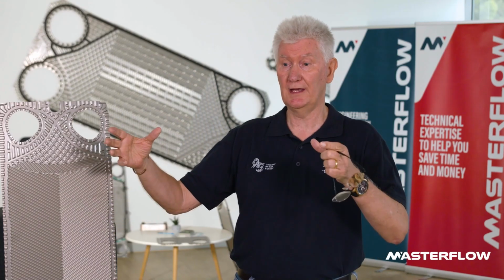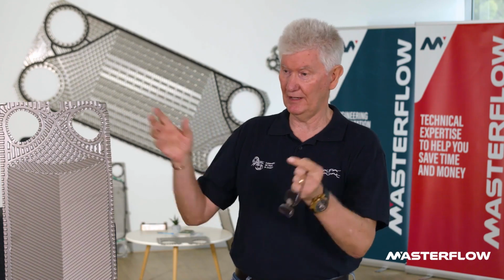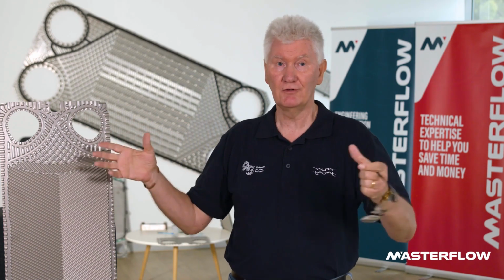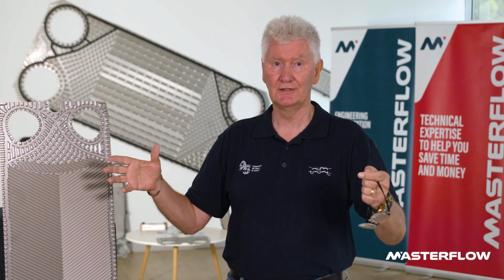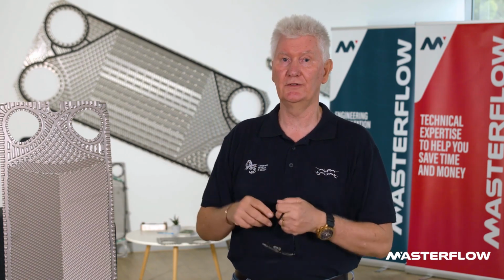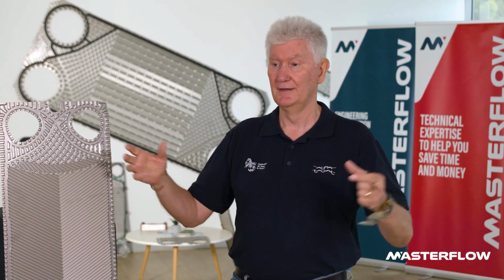If there's limited space, you're better off with high pressure drop, because that means the heat exchanger gets smaller. And there could either be fewer heat transfer plates in the same frame, or you'd be able to change the channel gap, or even shrink the size of the heat exchanger. And this is what we've done in the past. Clients have come to us and said, I've got 10 kPa and I have limited space. No heat exchanger will fit in there because it's just not enough space. So we can get them to compromise on the design pressure drop, and we can shrink the heat exchanger down to fit.